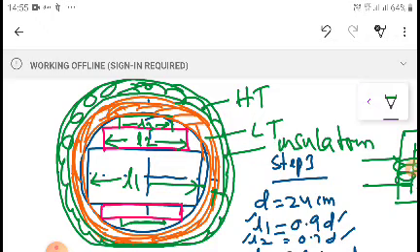In between there is some insulating material inserted as support, to create the air gap between the LT winding and HT winding, through which oil is circulated for cooling purposes. So this is the sectional plan of the limb.